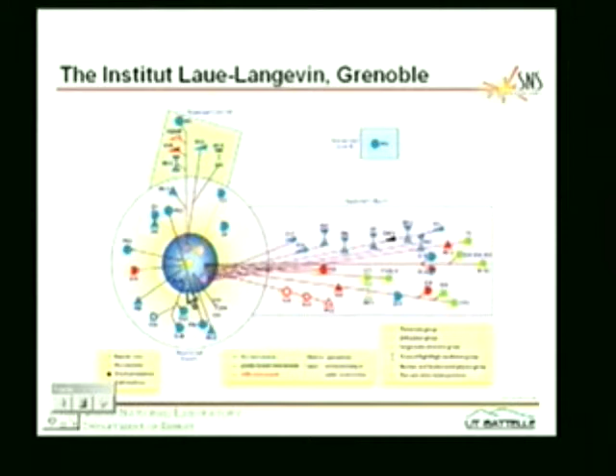It's got two cold sources. This is the newest one, a great big liquid deuterium cold source. It's also got a hot source, which is just a lump of graphite placed adjacent to the reactor core, and it gets heated up by the gammas to about 1500 degrees, which shifts the Maxwellian spectrum the other way. So if you want short wavelength neutrons, you sit on the hot source. If you want cold long wavelength neutrons, you sit on the cold source, and if you can't make up your mind, there's thermal beams as well.